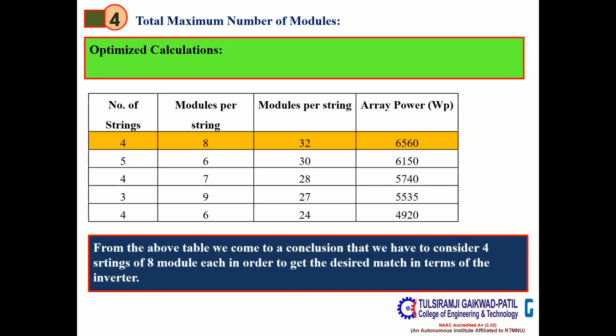Next, please. In the next slide, we will see how we then optimize this particular system. Here you can see in the first column the number of strings I have inserted, in the second column modules per string, and in the third column the total number of modules. Please correct it here, that would be the total number of modules. In the first column you can see the number of strings. Whatever calculations we have done in steps 1, 2, 3 and 4, we have come to the conclusion that the number of strings cannot be more than 6, right? That is the reason I have taken here 4, 5, 4, 3, 4. These are the combinations which I have taken here.